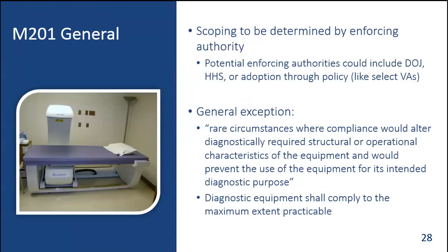There is also a general exception in M201.2. Medical diagnostic equipment is not required to comply with one or more of the applicable requirements in the MDE standards in the rare circumstances where compliance would alter diagnostically required structural or operational characteristics of the equipment and would prevent the use of the equipment for its intended diagnostic purpose. Even with this general exception, diagnostic equipment shall comply to the maximum extent practicable.